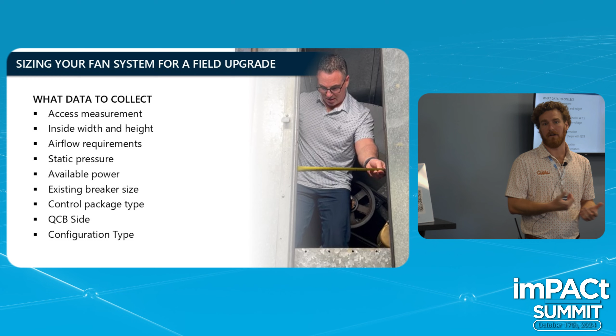Some sizing limits. In general, I think Q-PAC is a great product for supply fans, for chilled water air handlers, if you're between 2 and 8 inches of static pressure and I said 8,000 CFM here. Really, you can go as low as 5,000. But when you get under 10,000 CFM, you usually only need one Q-PAC or one ECM plug fan to do the work of that fan, so you lose the inherent redundancy of the system. So I tend to say if you can go up closer to 10, 15, 20,000 CFM at your entry point, that's where you get a 3 or 4 fan system, and the redundancy really helps.